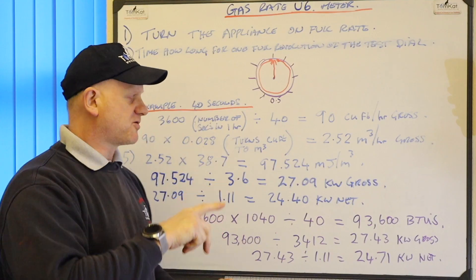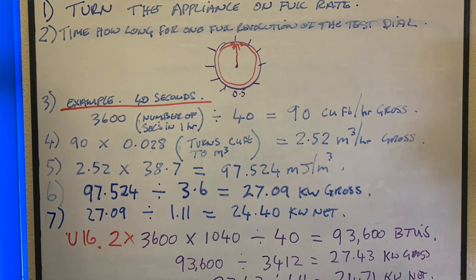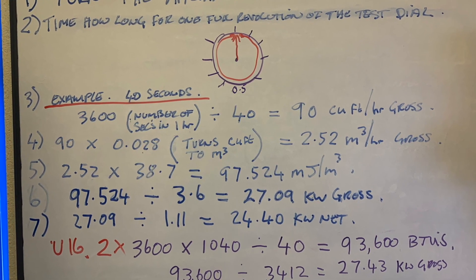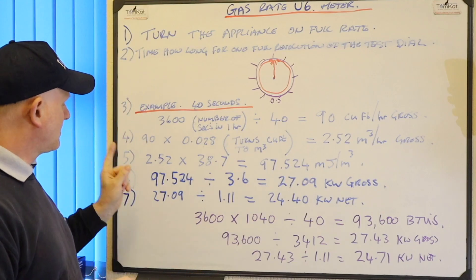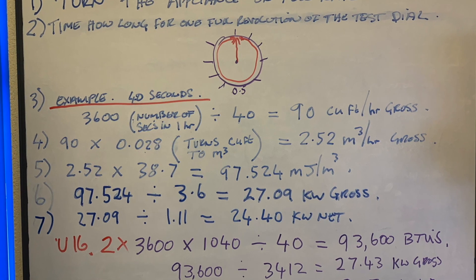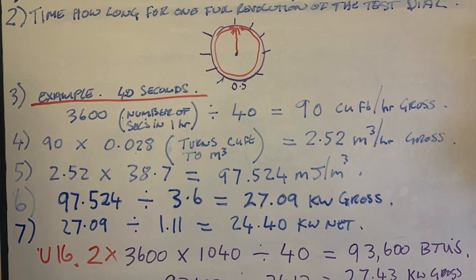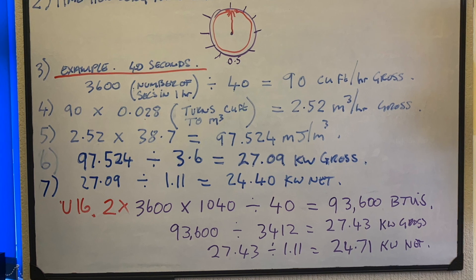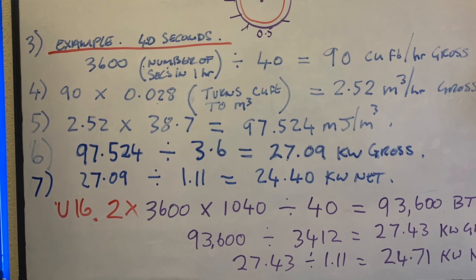Then we can revert back to what we did for the G4 - we can take the 2.52 and times it by the calorific value of gas which is 38.7, which comes out at 97.524 megajoules. Then we can take this 97.524 and divide it by 3.6, because there are 3.6 megajoules in a kilowatt, and it comes out at 27.09 kilowatts gross. We can then take this 27.09 divided by 1.11, which gives us 24.4 kilowatts net. That is what we class the longhand way of doing it.